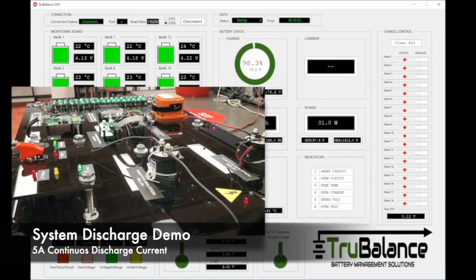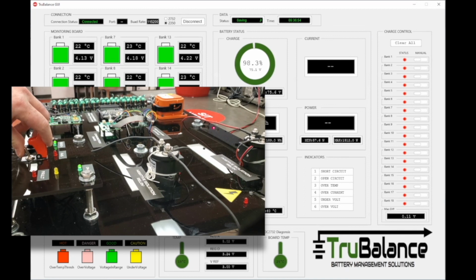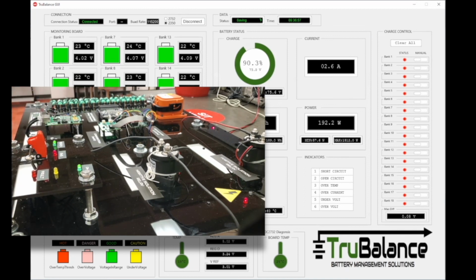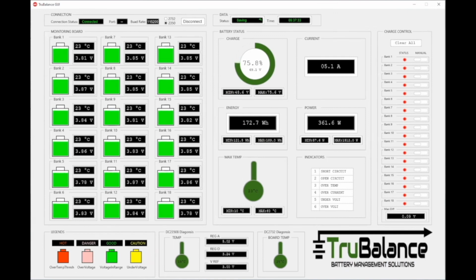For this demo, we show full operation of our system and GUI. We used an electronic load to control our discharge of the system at 5 amps, which relates to 2 times the C rate of our 2500 milliamp hour cells. During the discharge, we can see the GUI actively monitoring module state of charge, the voltage and temperature of the individual cells, the current and power being supplied, and the energy remaining in the battery module.